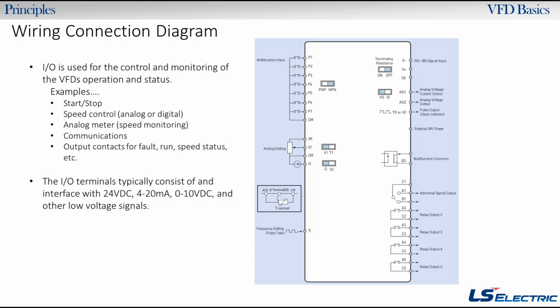Next thing that would be commonly wired up would be your speed control. That could be analog speed control, or it could be a digital preset. Looking at analogs, on our drives in particular, we have a V1, which is a voltage, an I2, which is a current, and then we have a CM, which is your common. For most of our drives, we use CM as a common terminal. Common is just required to close the loop for your analog or digital signals. Most speed control is a 0 to 10 volt DC signal or a 4 to 20 milliamp signal. So V for voltage, I for current. That's where you'd wire those up. You could also do a speed pot. You'd also have your I/O working for your communications. For communications, that would go to S plus and S minus over here.